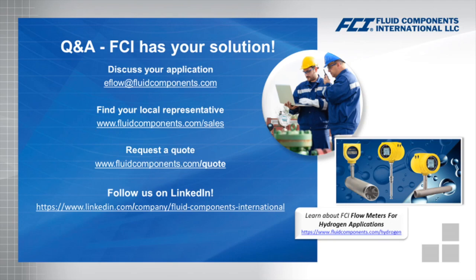What we see is probably a bigger influence is a control valve that is modulating, not necessarily on-off. If something's modulating and it's upstream of the meter, it can introduce a very large error depending upon its proximity to the meter itself. Guidelines, I think, within the industry is the preference is to put those types of control valves downstream, and that way it minimizes the influence.